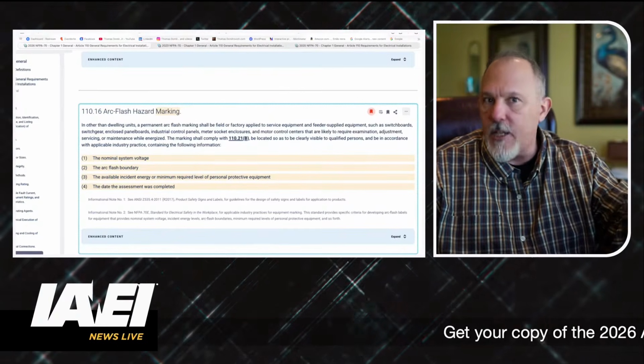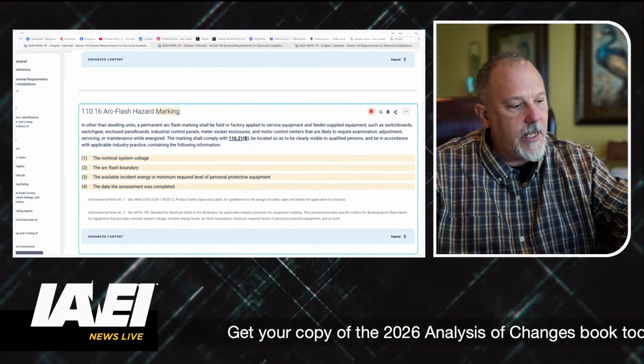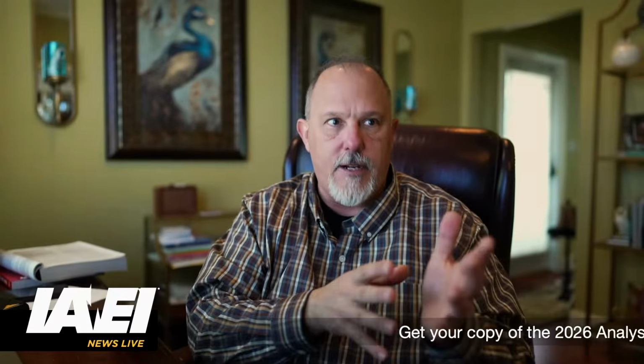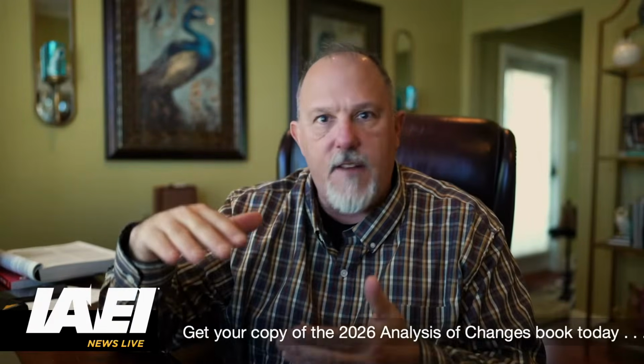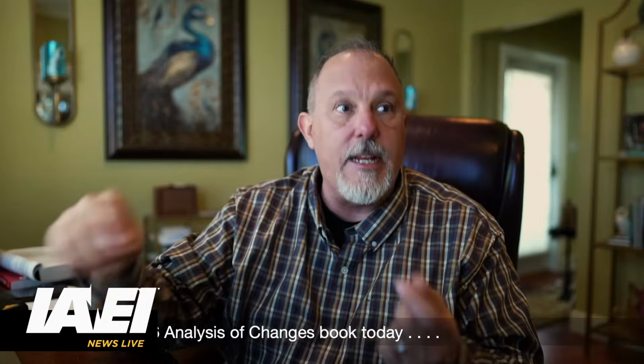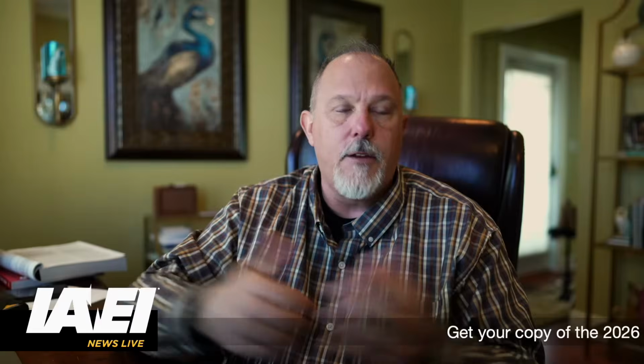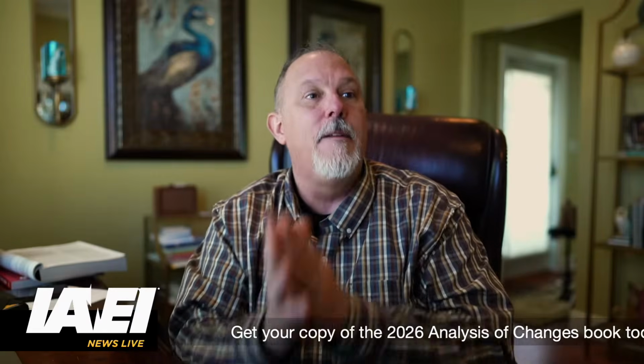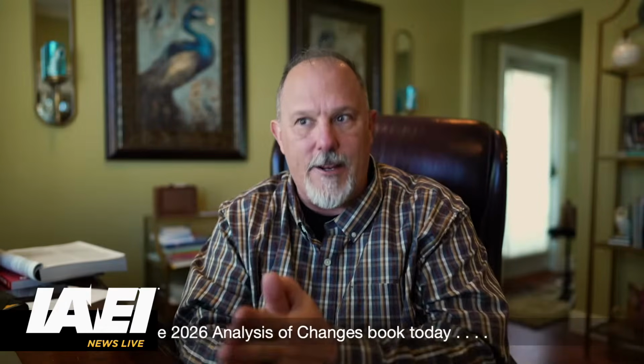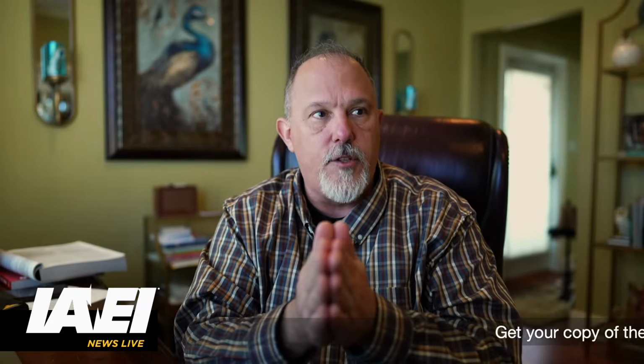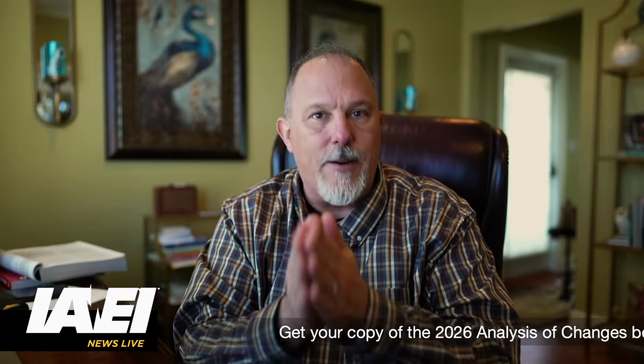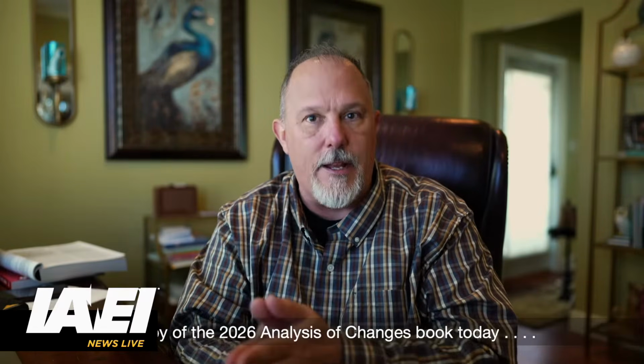But if it's in an industrial establishment, a commercial facility, that language is generic enough to say, look, I don't have a voltage cutoff, I don't have a current cutoff. If it's feeder supplied equipment, such as switchboards, panel boards, switchgear, motor control centers, meter socket enclosures, that would require, and this is the other caveat, examination, adjustment, servicing, or maintenance while energized. Let's talk about that for a second. Those are some interesting words: likely to require examination, adjustment, servicing, or maintenance while energized.